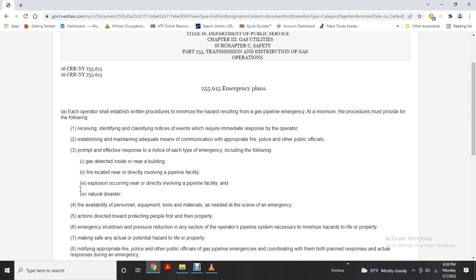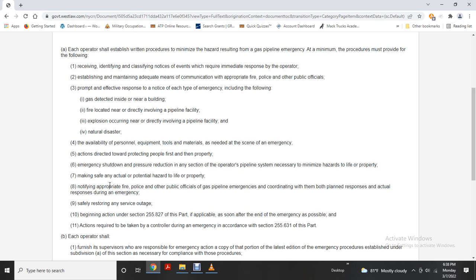Emergency plans. Each operator shall establish written procedures to minimize the hazard resulting from a gas pipeline emergency. At a minimum, the procedures must provide for receiving, identifying, and classifying notices of events which need immediate response by the operator. Establish and maintain adequate means of communication with appropriate fire, police, and other public officials. Prompt and effective response to each type of emergency, including the following: gas detected inside or near a building, fire located near or directly involved in a pipeline facility, explosion occurring near or directly involved in a pipeline facility, and natural disaster. The availability of personnel, equipment, tools, and materials as needed at the scene of an emergency. Actions directed toward protecting people first and then property.